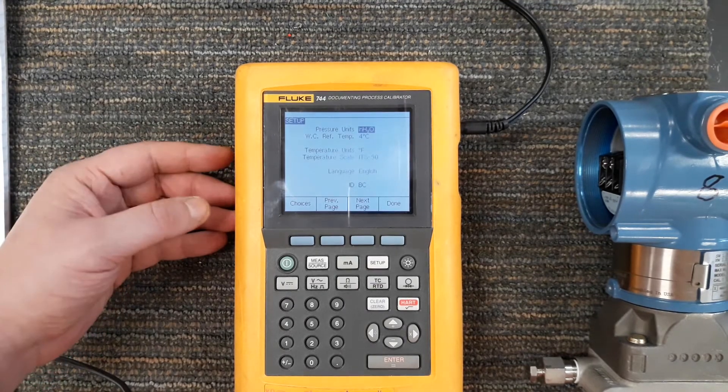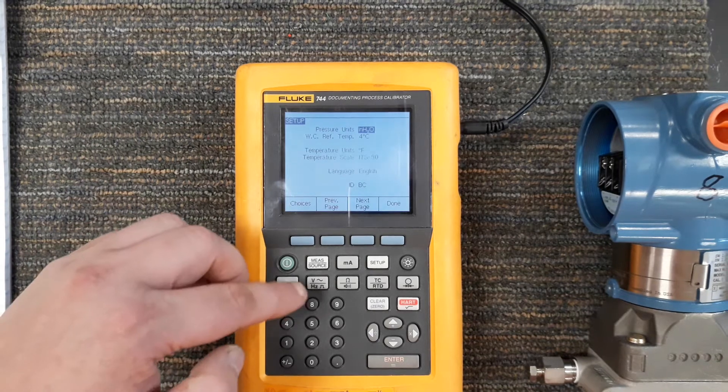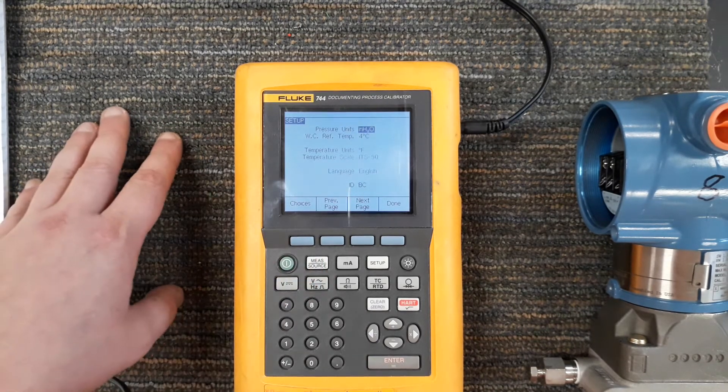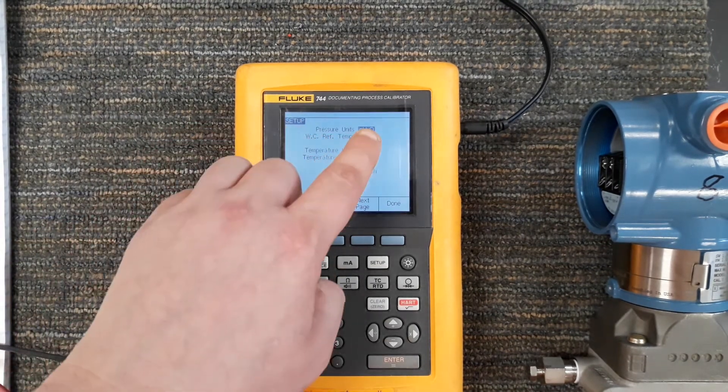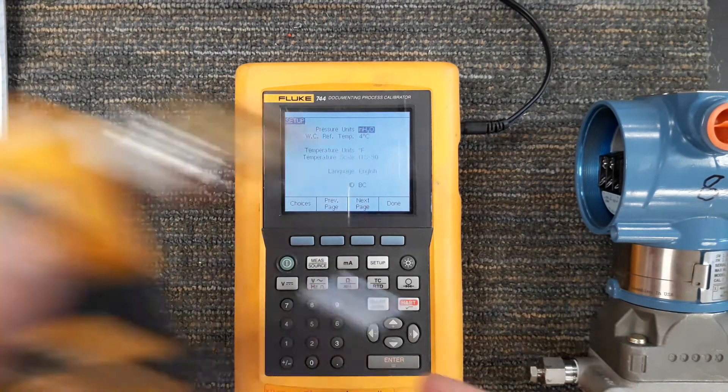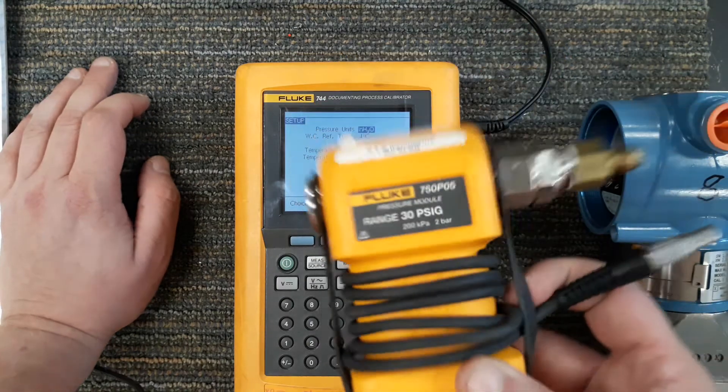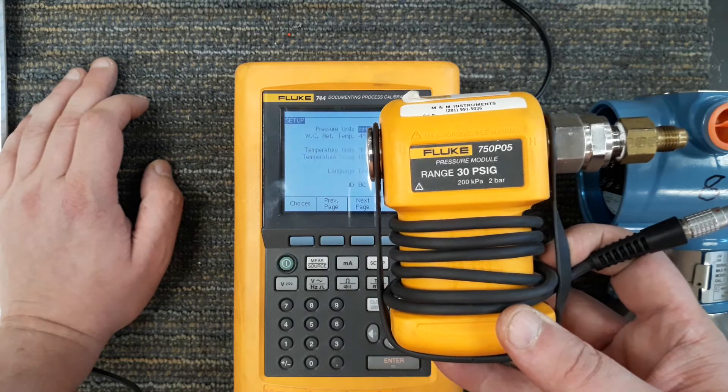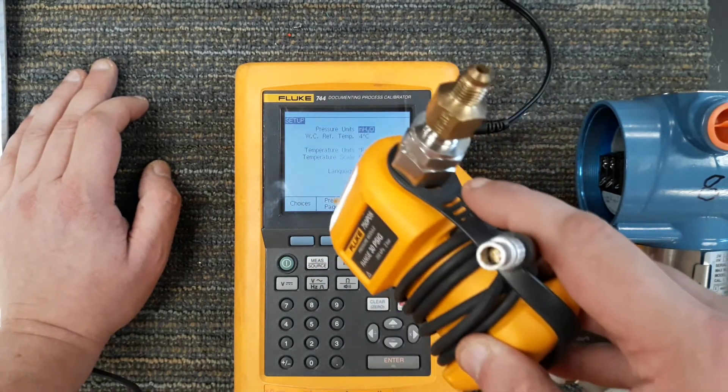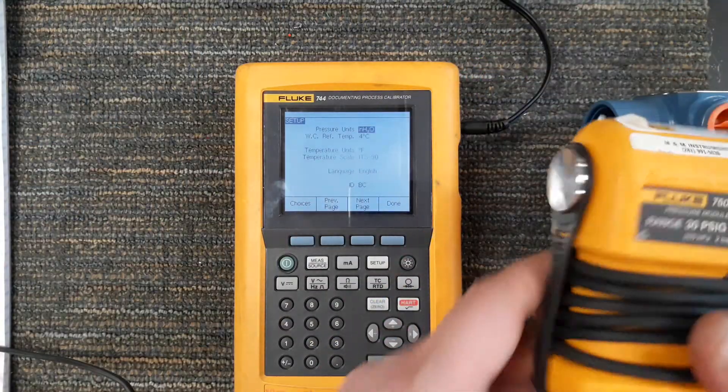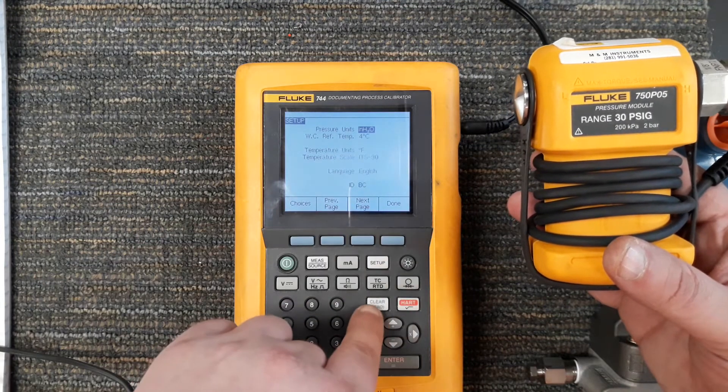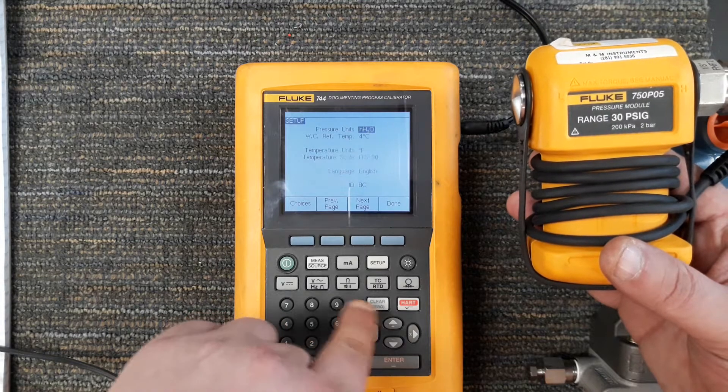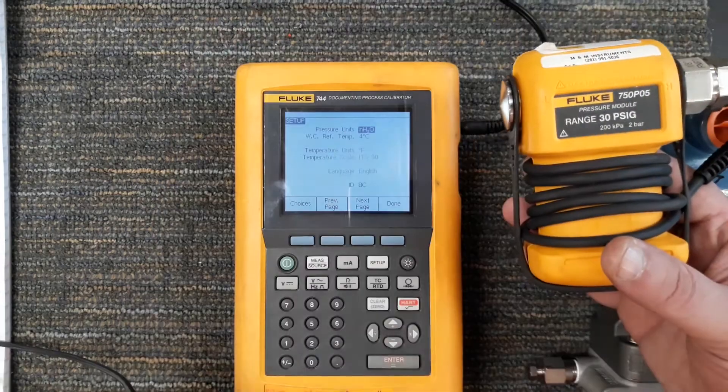You see it's May 6th of 2020 and the time is 8:37 in the morning. Hit next page, here's where I can set up things related to pressure or temperature, my units. So if I want to measure pressure this is the unit it's gonna make the measurement in. And again as I told you earlier if I wanted to source pressure with the Fluke 744 I need an external pressure sensor in this case the Fluke 750 P05 and I showed you how to connect it in the previous video. Once this connects, it boots up, you're gonna hit this zero button which was the clear button. It zeroes out whatever this is seeing so you can say that that's my atmospheric reference zero psi G.